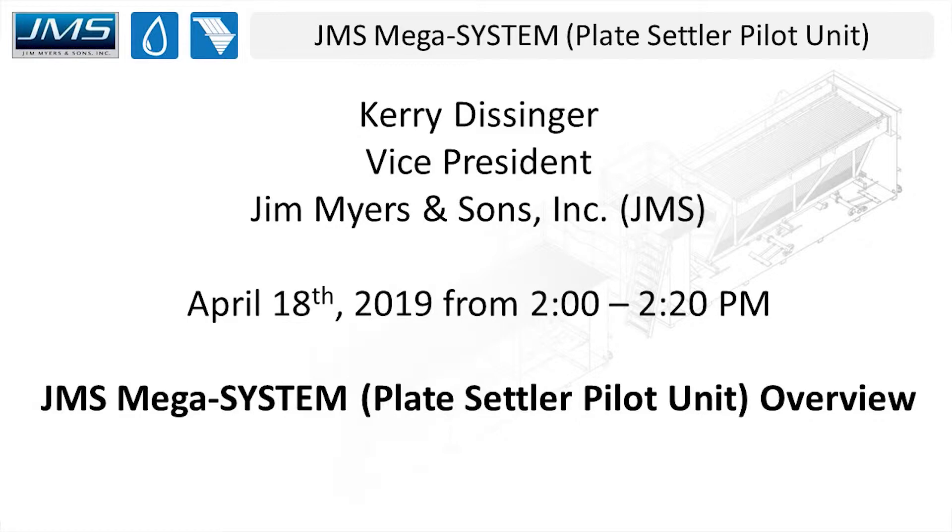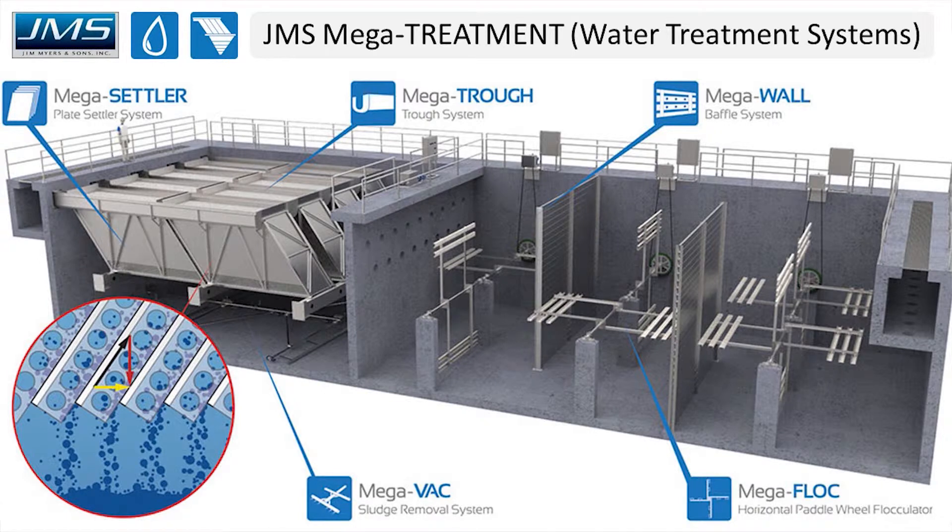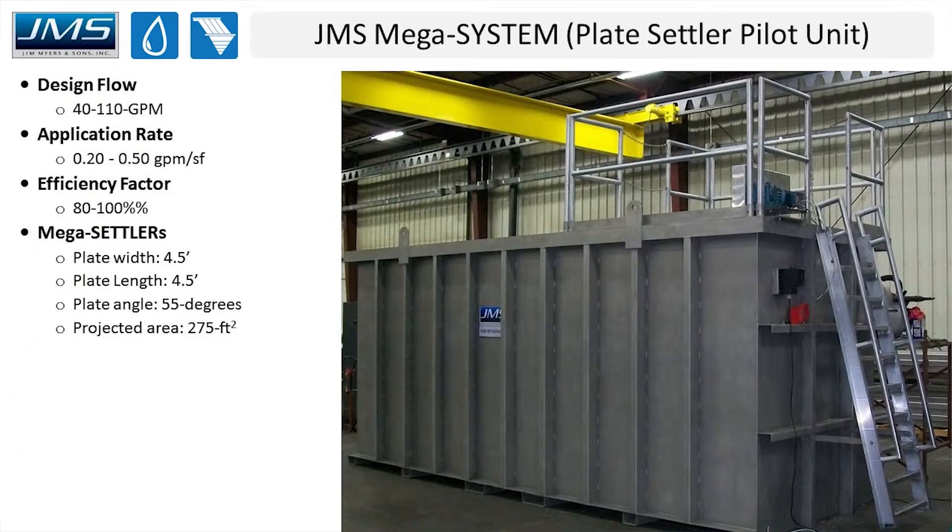Over the next 15 to 20 minutes I'm just going to give a general overview of the JMS plate settler and our plate settler pilot system. The pilot system is designed to mimic a full-scale floc and sedimentation basin. Our unit includes inclined stainless steel plate settlers, horizontal paddle wheel flocculators, stainless steel Mega-WALL baffle system, and our Mega-VAC sludge removal system. It's a full stainless steel system designed for 40 to 110 gallons per minute. We can test different application rates on the plate settlers, typically ranging from 0.2 to 0.5, and we can also look at testing different efficiency factors.